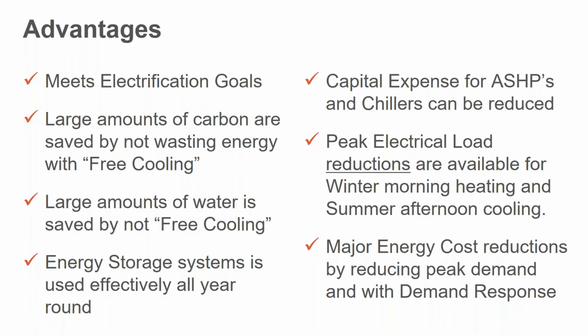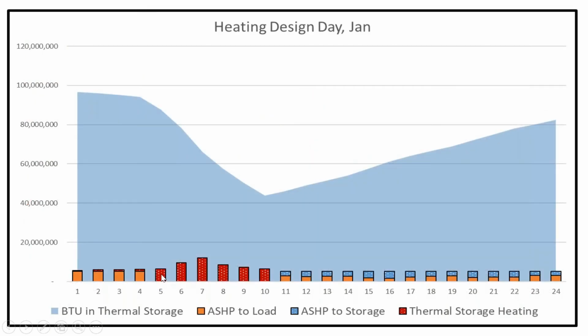The electric peak load reductions are available for winter and summer. So in the summer, I don't have to go into that explanation, but let's look at that period that we had right here. So now, instead of having air source heat pumps running at a COP of about 2 or 2.5 to meet the peak load of this building, at this point, we are running a centrifugal chiller making ice at a heating COP of about 5.5. So in comparison, as far as peak load reduction, you have cut the demand that you would have had in the building with the air source heat pumps in half or by more than in half.